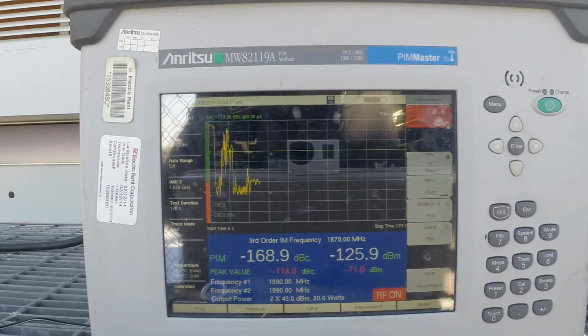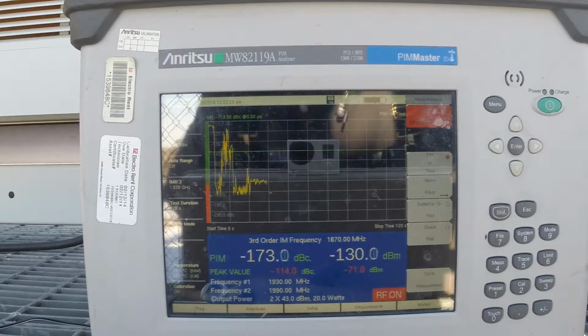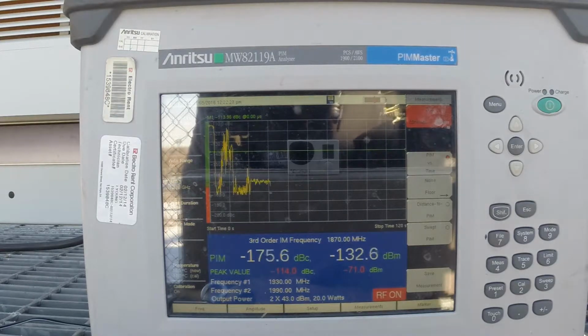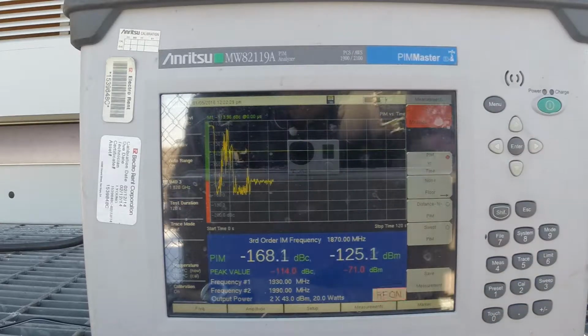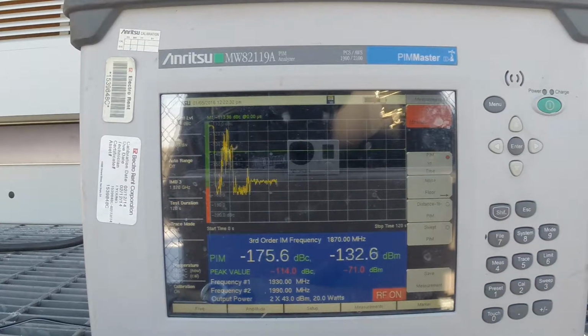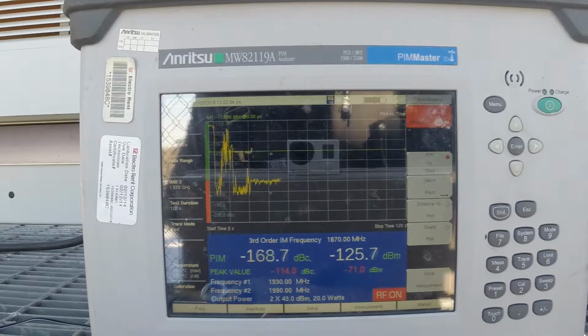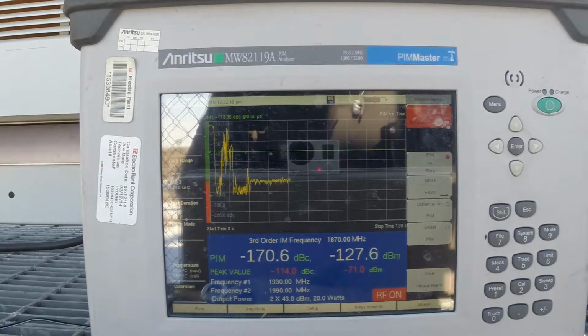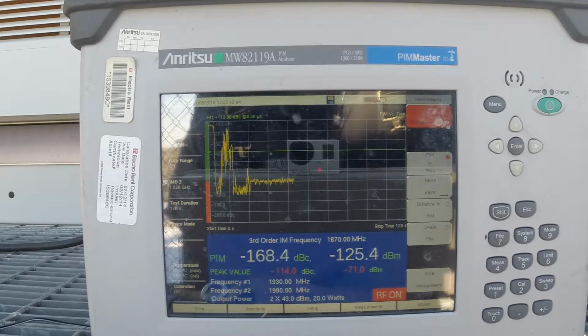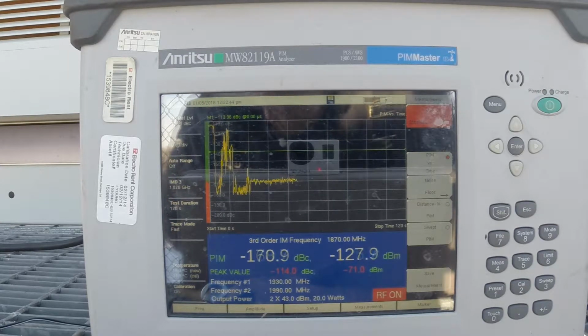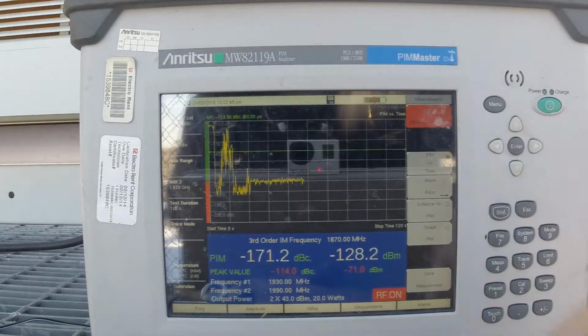Best thing to do is just rule out stuff. Get your distance to PIM, figure out if it's on the ground or on the tower. If it's on the ground, start tapping on connectors. See if you have PIMs move around like this. Tap on a connector, it moves, take off the weatherproofing, blow it out, torque it, see if it fixes it. If not, tap on it again, still doing the same thing. Go ahead and take apart the connector or replace it if it's a GMA press-on connector.